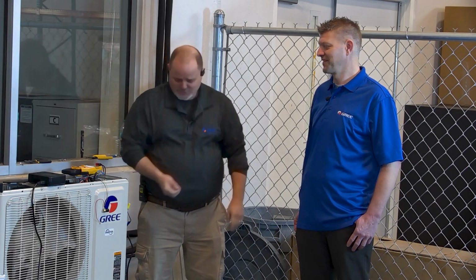The other thing that I was always taught when I first got into trade school, we were learning about taking temperatures of refrigerant lines. Why do we take the temperatures of the refrigerant lines? Back then, they didn't have temperature clamps that you just clamped on the refrigerant line. You had to strap on a thermometer, or you took a piece of metal tape and taped the thermocouple to it. Which is the same thing, if you think about it realistically, that GREE is doing with those thermistors. They are putting thermistors on the copper pipe, and that is your eyes and ears into the system.